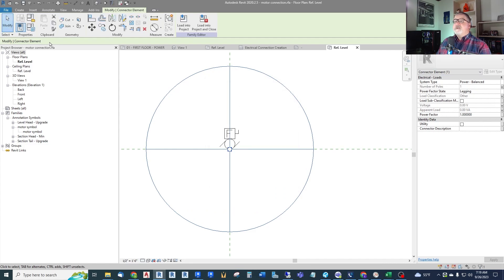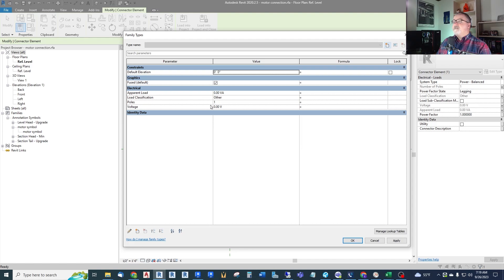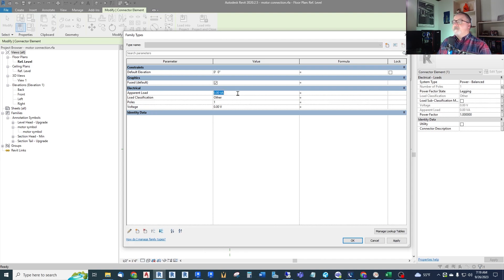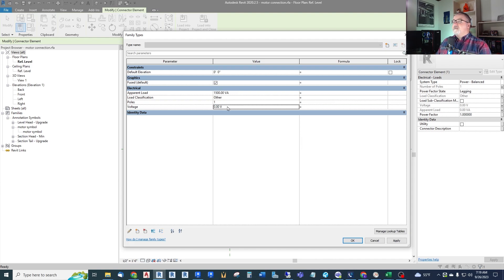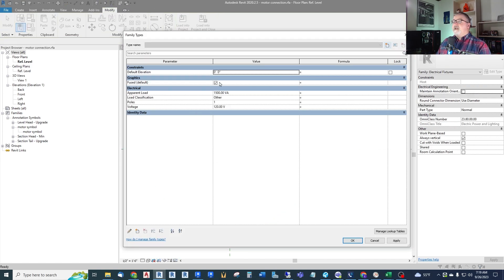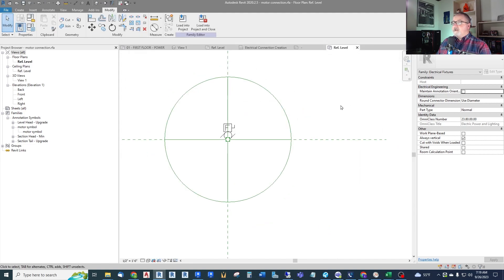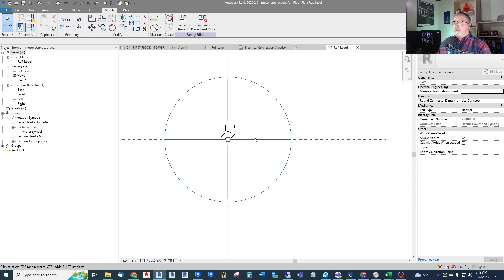We have the parameters we need. If you click here we can see that we have all the properties grouped under the electrical heading is what we were doing. So we have what we need. And we can change the order of these if we want. We can type in some defaults. I like to put some kind of a default in here. Let's go with a 120 volt. So this is just a simple single phase 120 volt motor as a default. And we have our fused visibility controls here. So we should be good there. This really is all there is to it. The trick is getting that annotative element made first and bringing it into our electrical model. So let's go ahead and save this as a motor connection.